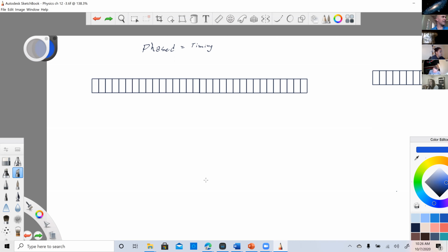Then we move forward. There's a number of pages that show steering and everything. I think we've gone over that fairly well. And then there's dynamic receive focusing, and then we move forward to an annular phased array. And then I'm going to jump all the way to the linear sequential array. Now, the original linear sequential arrays, the old fashioned ones, the bricks, weren't phased, they only sequenced. Those don't exist anymore. Now we have phasing and sequencing in our linears.